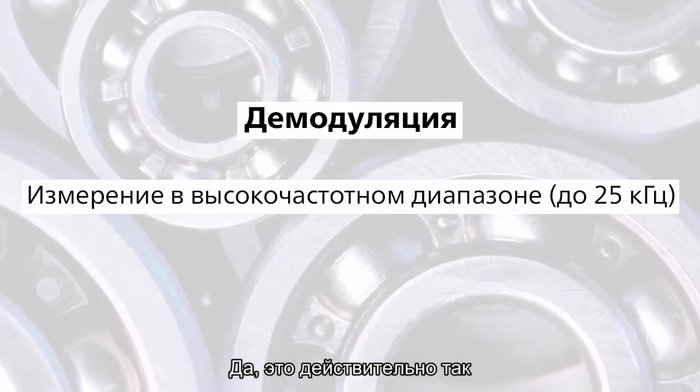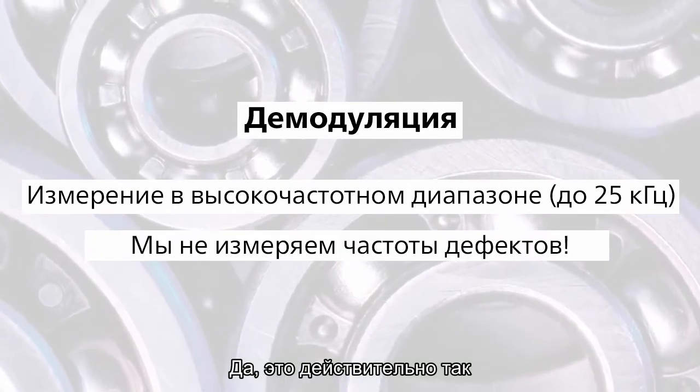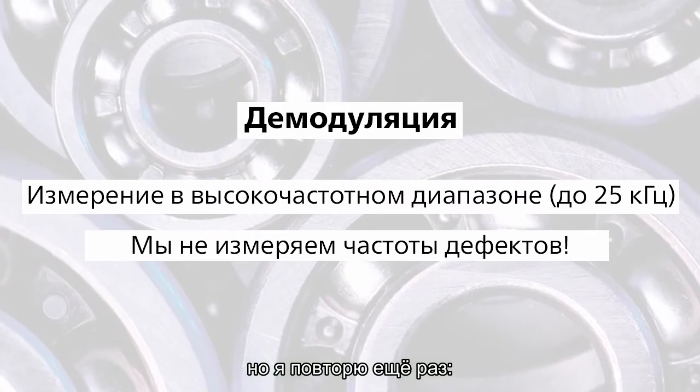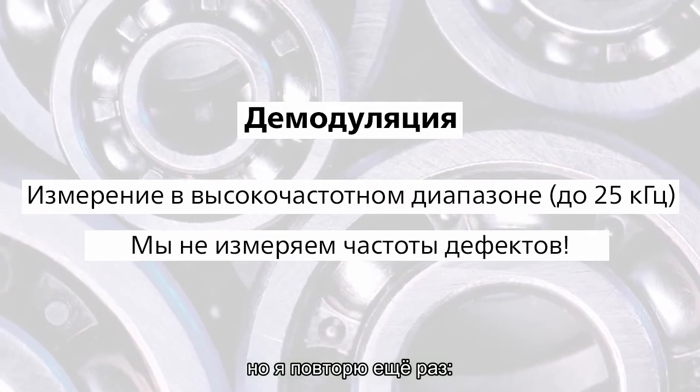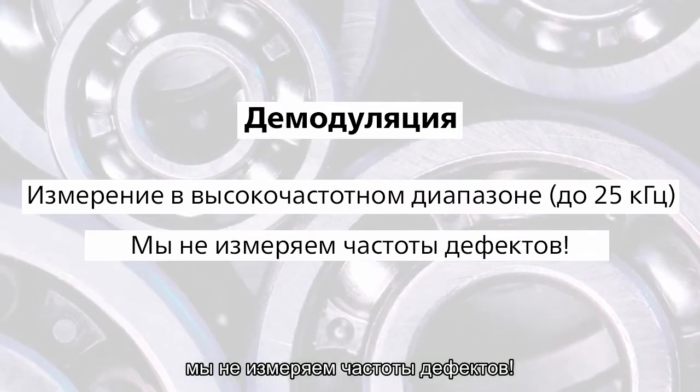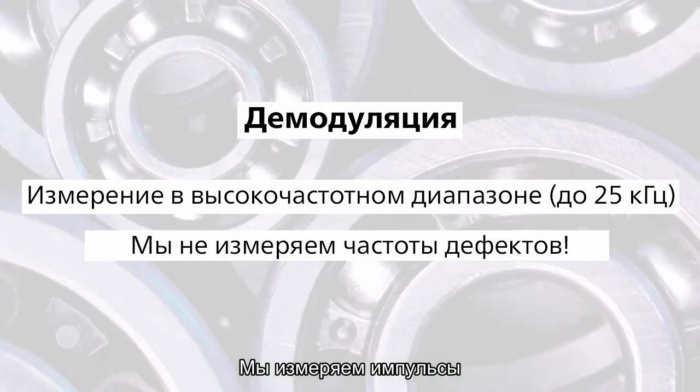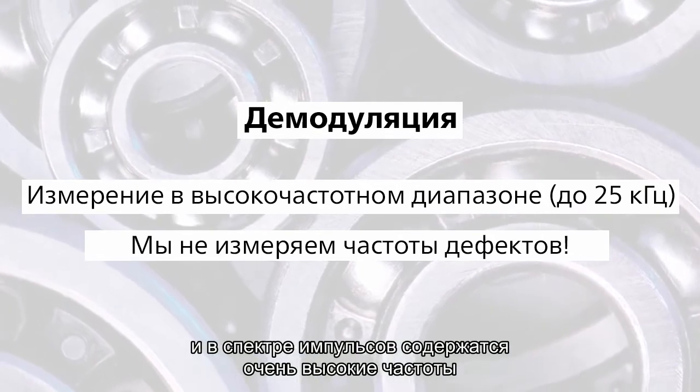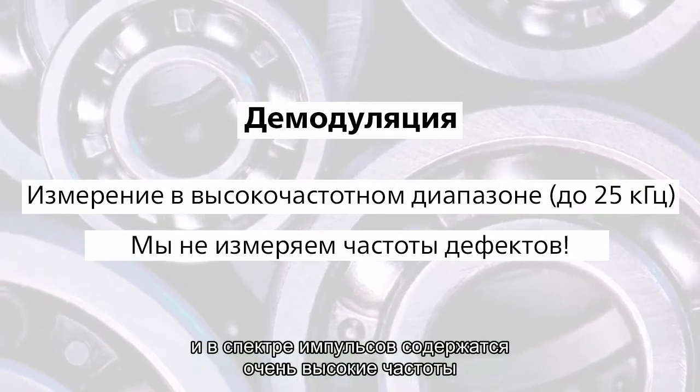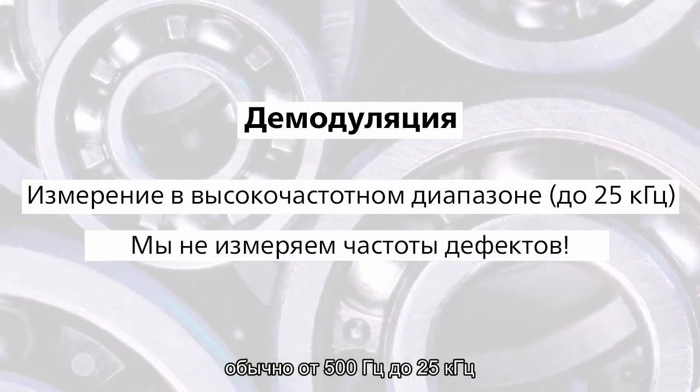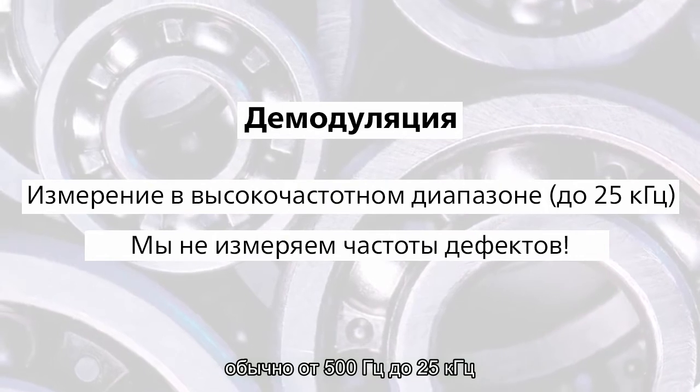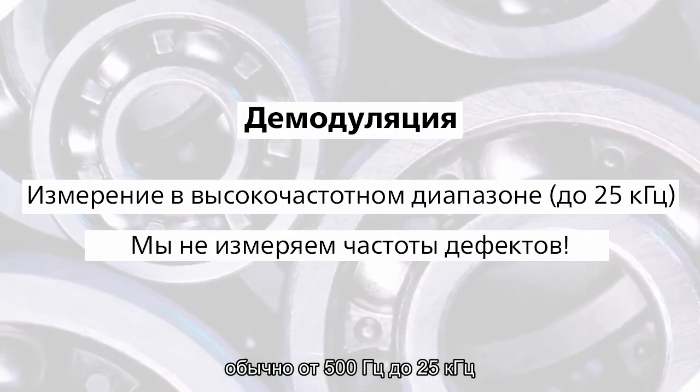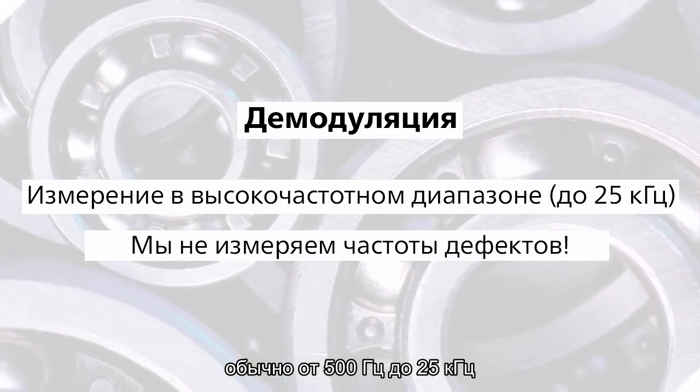Yes, it is true. But I repeat again. We don't measure the fault frequency. We measure shocks. And shocks contain very high frequencies, typically between 500 hertz and 25 kilohertz.